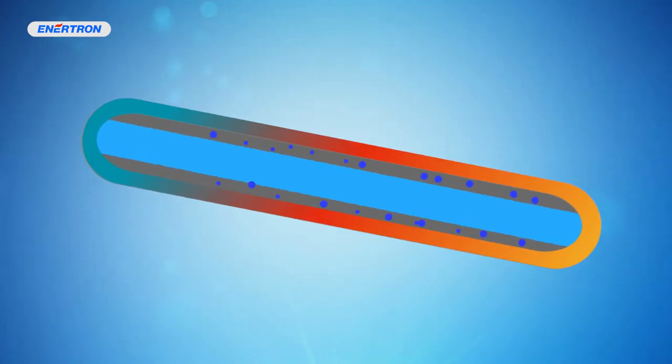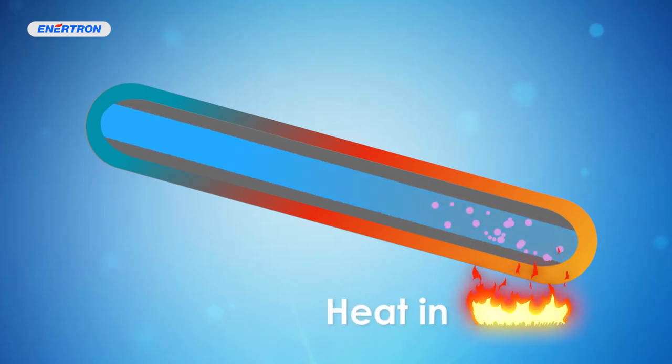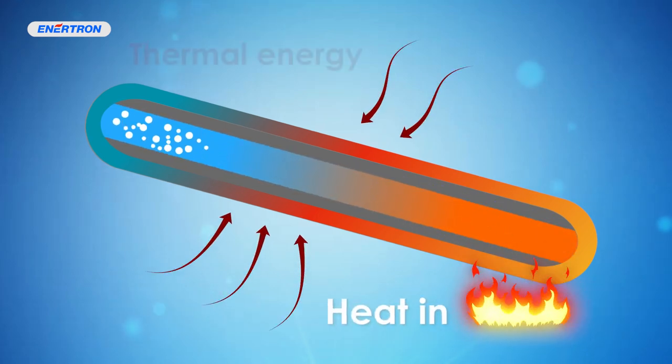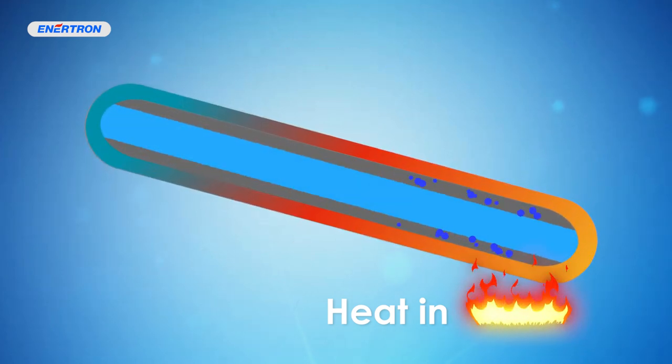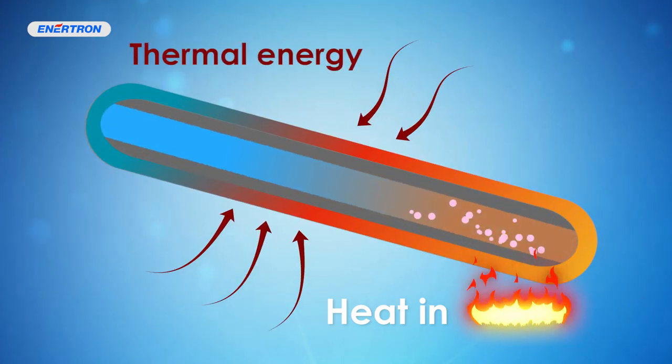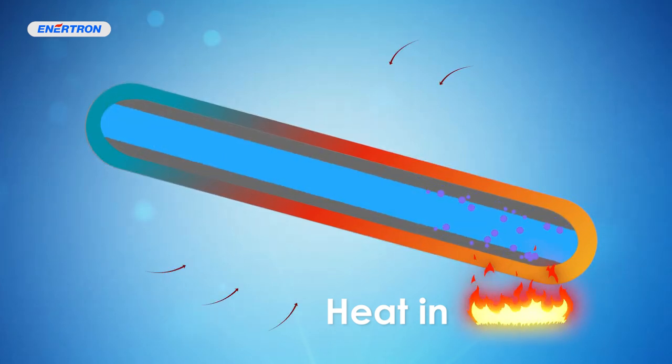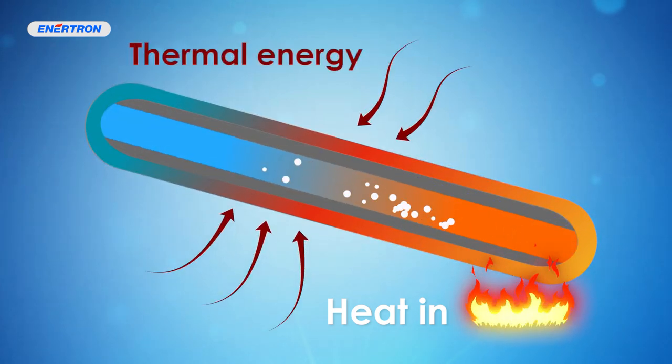When heat is inputted into one end of the heat pipe, the working fluid begins to boil and absorb large amounts of heat using only a small amount of working fluid. During this process, the phase change to vapor occurs with no change to the temperature inside the heat pipe vessel. This change from liquid phase to vapor phase is called latent heat of evaporation.